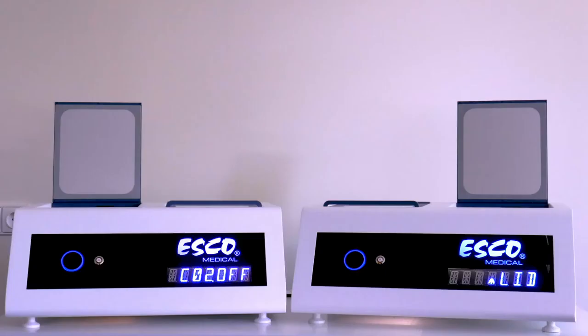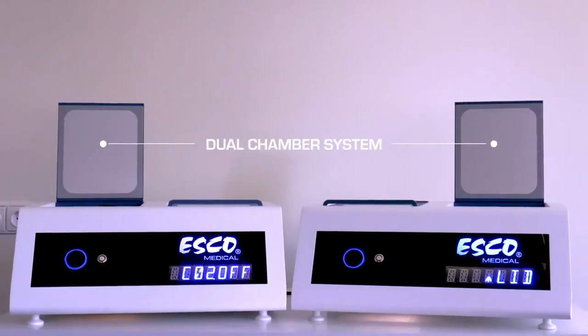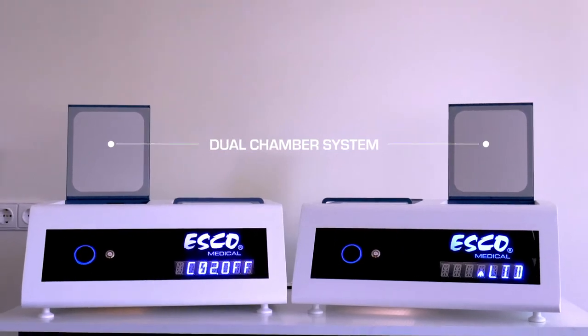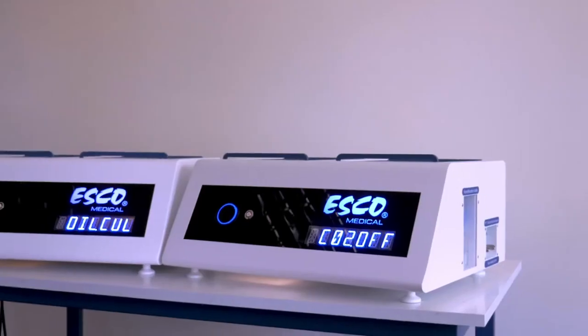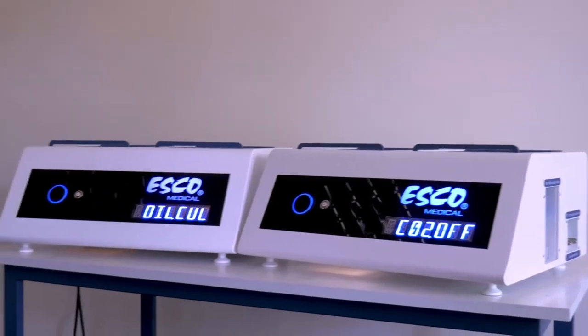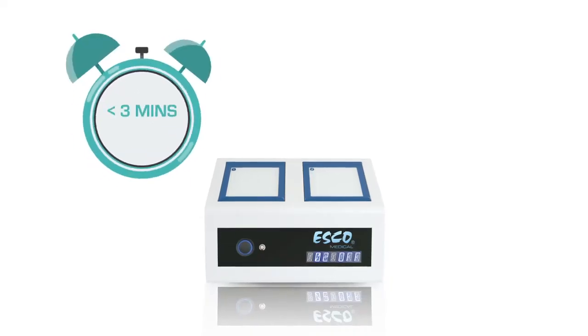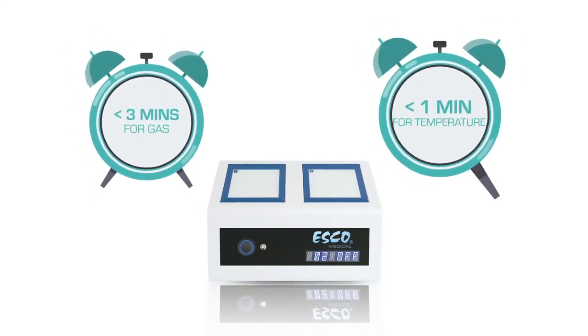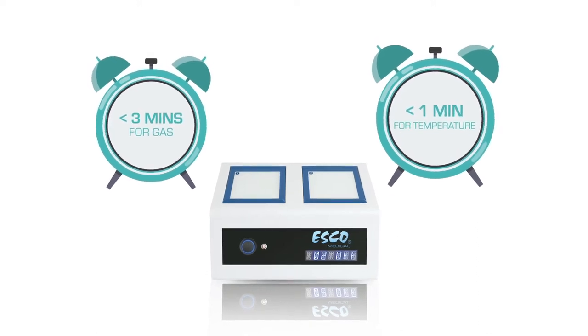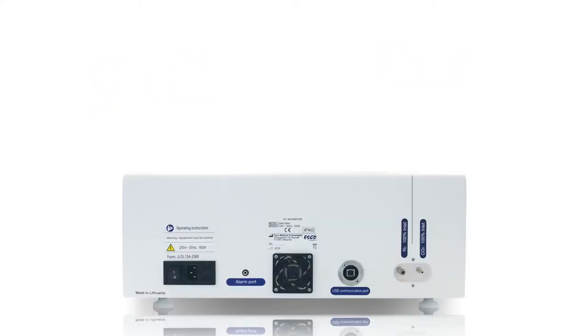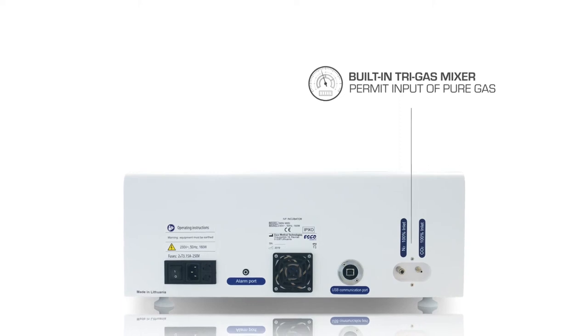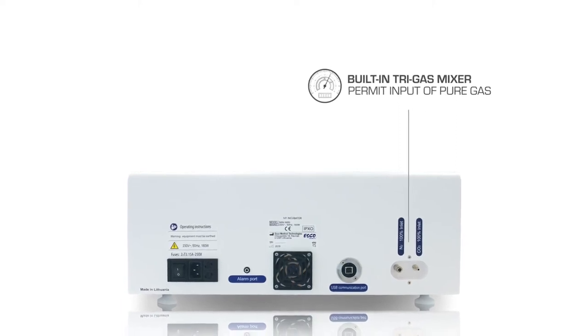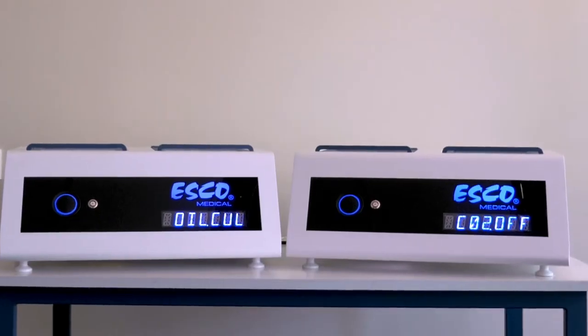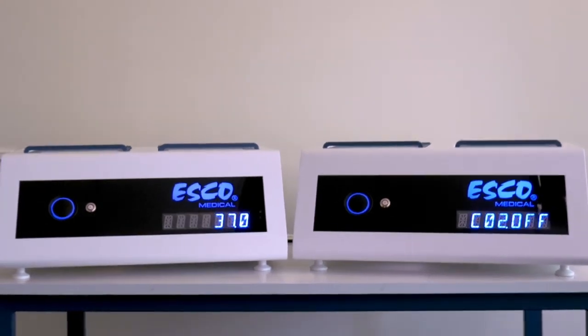The Mini Miri has a dual-chamber system with heated lids to prevent condensation and improve uniformity and recovery. The robust Miri design guarantees fast recoveries. At less than 3 minutes for gas recovery and less than a minute for temperature, bid expensive pre-mixed gases goodbye. The built-in tri-gas mixer and carbon dioxide and oxygen sensors permit input of pure gases and accurate control of gas phase composition within the chambers.